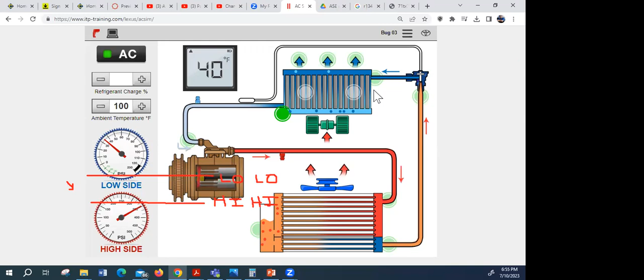It's drawing the refrigerant down, so it's going to bring it to a lower temperature than it should be. I agree with you. But what would that cause on the high side? Higher pressure, right? Because it's pumping like crazy, so it'd bring it up to higher pressure.